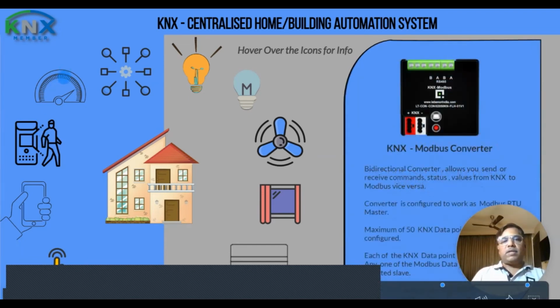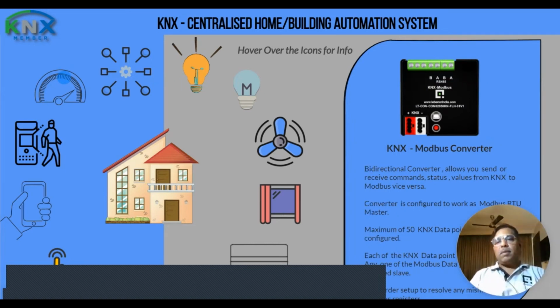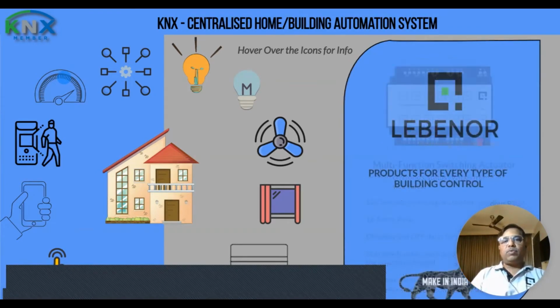KNX to Modbus converter. This Modbus converter supports 50 data points, and this was mainly developed so that, in the true sense, all our system integrators should be able to offer energy management or energy monitoring solutions to all their customers. Up to 4 energy meters can be connected to this module, and all the important data points will be made available in KNX.